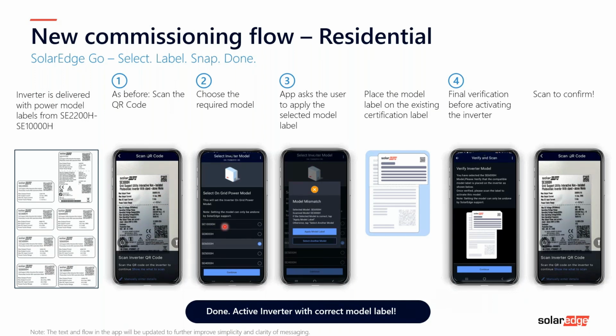Then you get the option of choosing your power class. You can see on here that you've got the 10, the 8, the 6, and 5, and 4, and the rest are underneath, we'll see later in the video anyway. You simply select, highlight the one you want, press continue, and then it says apply model label, and that's where you select the one you want. You put it on top of this one here, and then you press that button, and it says prove that you've installed the right label, just to make sure that you're not going to put a 6 kilowatt on a site that should only be a G98. So you prove the label and put it on, and then you have to take a scan of the 2 labels again, just to check that it's got the right power class label.